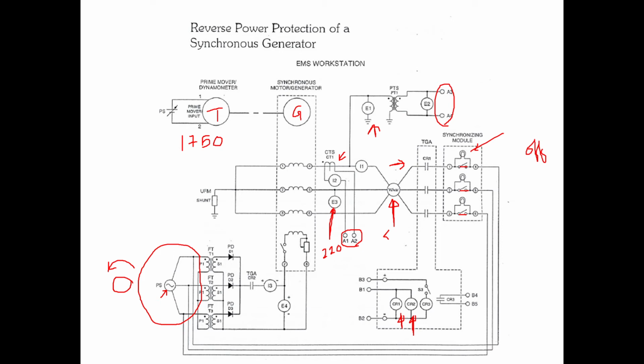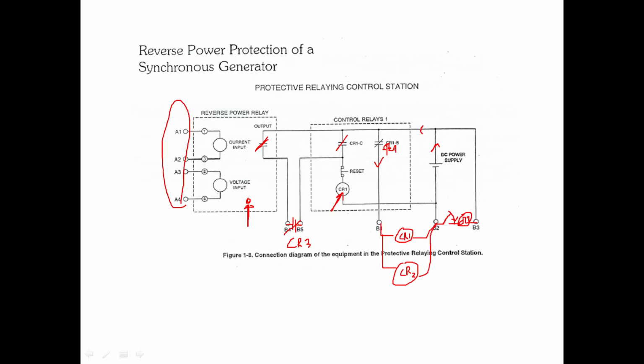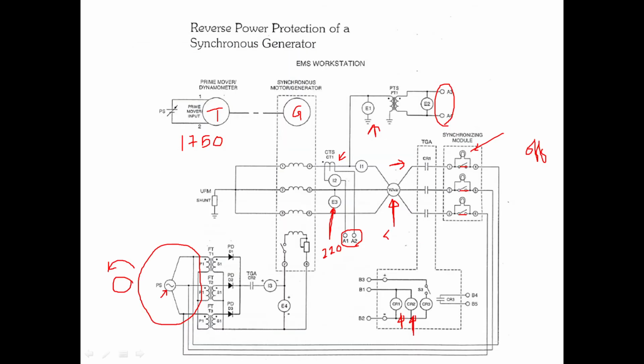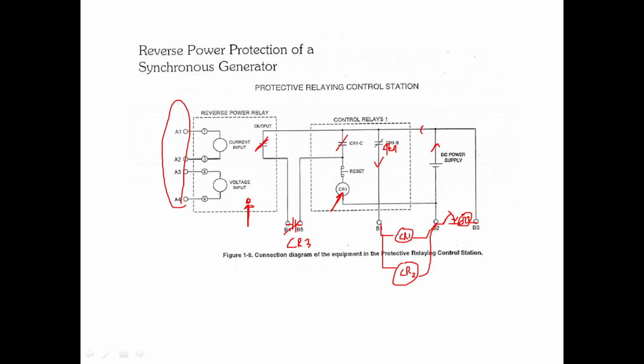The circuit is very simple. Two things you have to understand: how to create a fault, and the control action. Here we are creating the fault by playing with the supply. When you bring this to zero, you can monitor this wattmeter. The direction will change. When the direction changes, this relay output will be closed, and when you manually close the CR3 contact, CR1 and CR2 will energize. So the fault is created by playing with the supply, and the control action is opening CR1 and CR2 to isolate the generator from the grid. So this is reverse power protection.